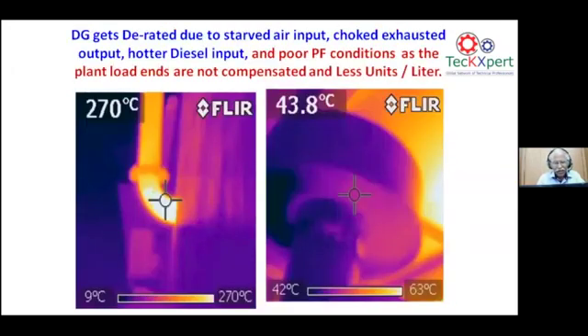This is an area where you use a thermal imager. As I was telling you before, on the process side, try to use your thermal imager. The generator got derated because at the delivery end, when the generator was running in the case study, we found this bend showing 270 degrees. It was totally choked and the back pressure was more. It is not monitored. Once we noticed this, we told the industry, they removed the L bend and put a T connection, kept an inspection point, and removed the choke in that line. The generator came back to full capacity.